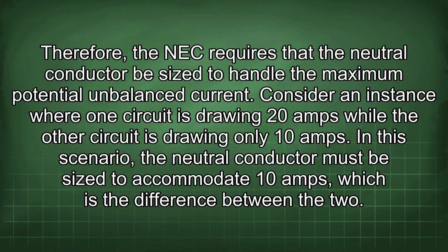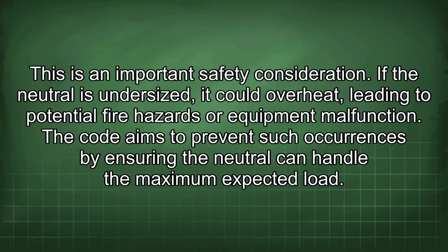Consider an instance where one circuit is drawing 20 amps while the other circuit is drawing only 10 amps. In this scenario, the neutral conductor must be sized to accommodate 10 amps, which is the difference between the two. This is an important safety consideration. If the neutral is undersized, it could overheat, leading to potential fire hazards or equipment malfunction. The code aims to prevent such occurrences by ensuring the neutral can handle the maximum expected load.